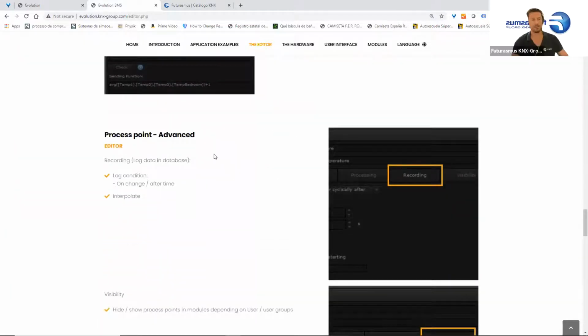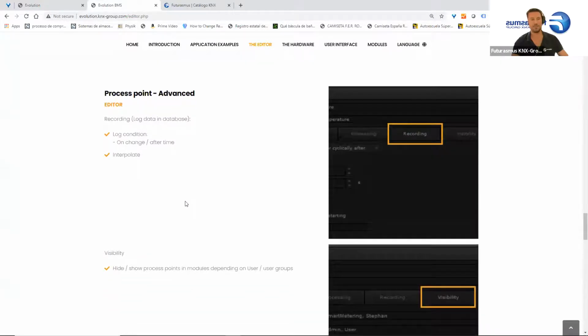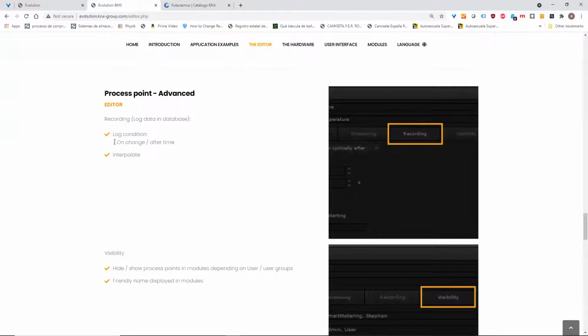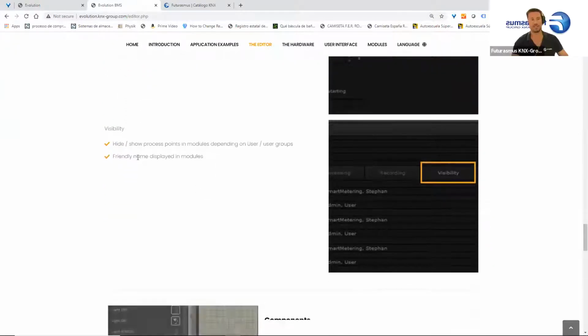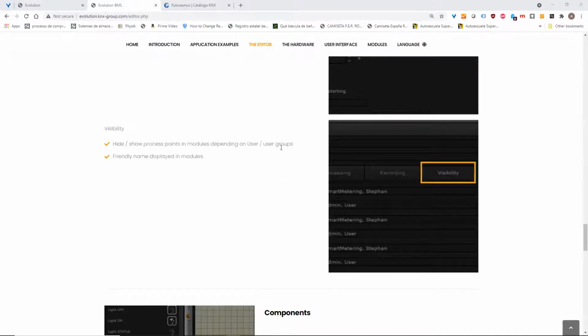In the recording function, you can set whether the log data should be interpolated or not, and whether it should be logged on change or after a certain time. There's also visibility settings for different user groups - for example, maintenance process points might not be visible to normal users, while maintenance staff will have different visibility rights.